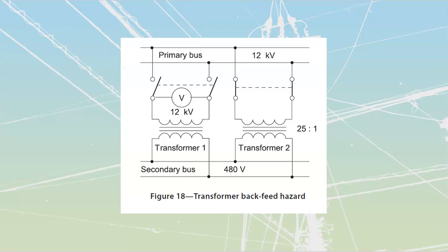And the reason we need that is simply because we need to be able to isolate, particularly for this transformer backfeed hazard. Do transformers work in both directions? Absolutely, transformers do work in both directions, which means I can feed a low voltage in and get a high voltage out, or I can feed a high voltage in and get a low voltage out.